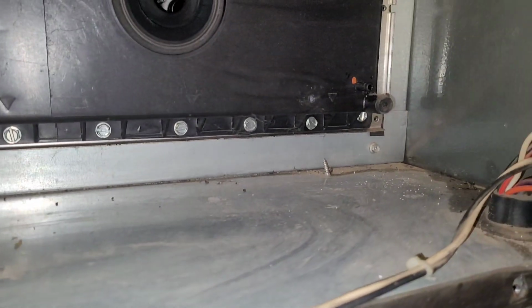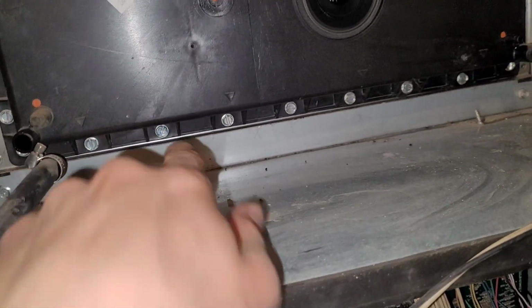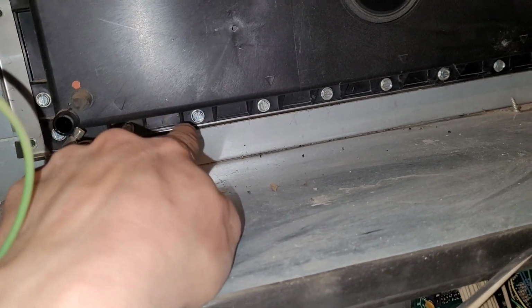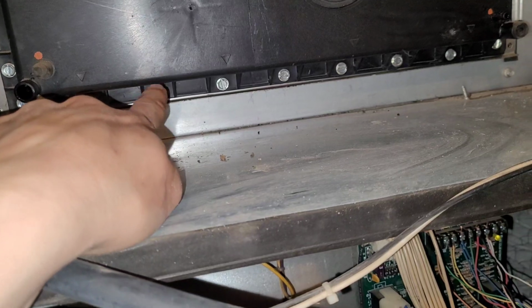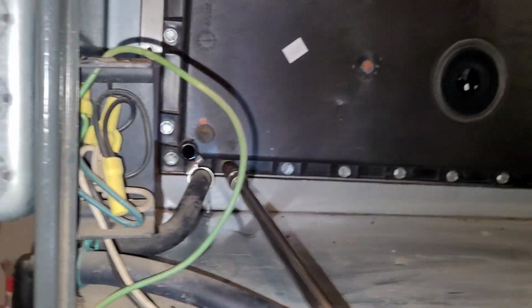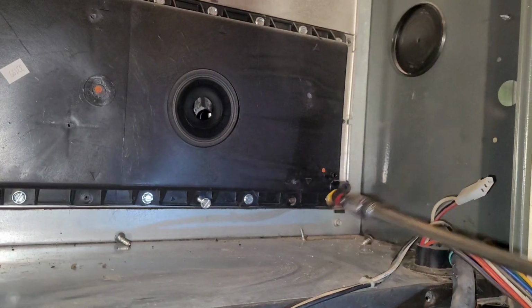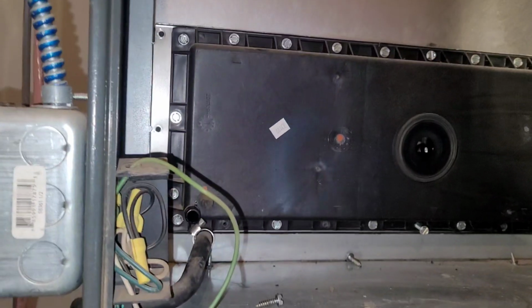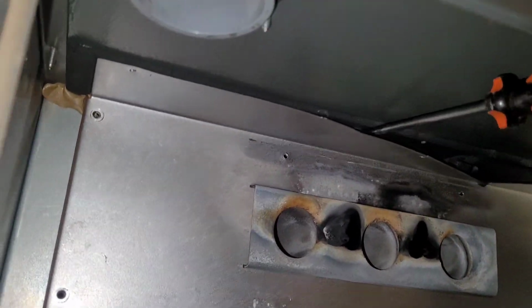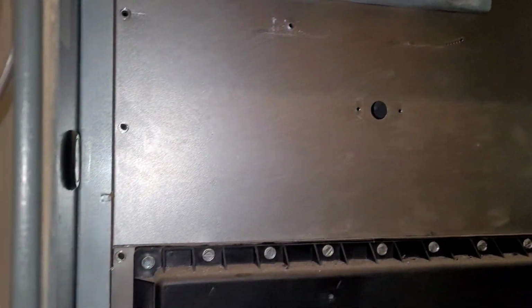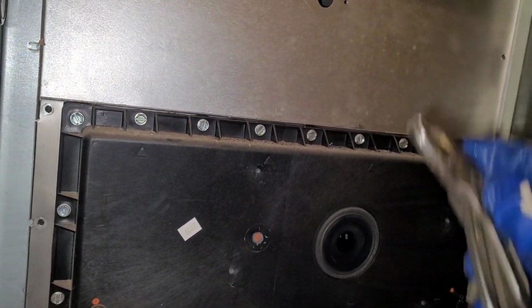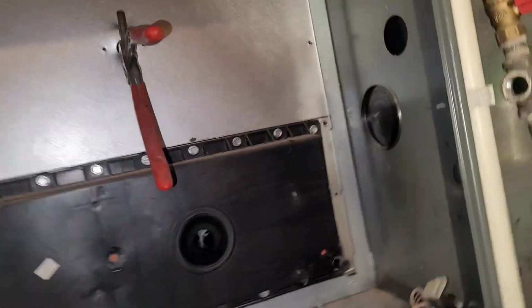To actually get the heat exchanger pulled out along the bottom, you only need to remove the screws below these little indicators every other, because these are the ones that actually tie into this plate. This plate kind of has like a castle shape, so it's cut down so this screw doesn't go into this plate, but this one does, this one doesn't, this one does. So you really only have to remove every other along the bottom here. And of course the ones up the sides, across the top, and down the other side. Use a screwdriver to break the foam gasket free along the top, and I usually take a channel lock and I just grab it into where the limit switch is and I begin pulling, but usually it's a little difficult to get it removed.